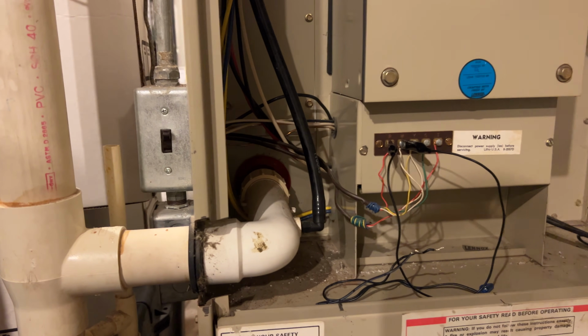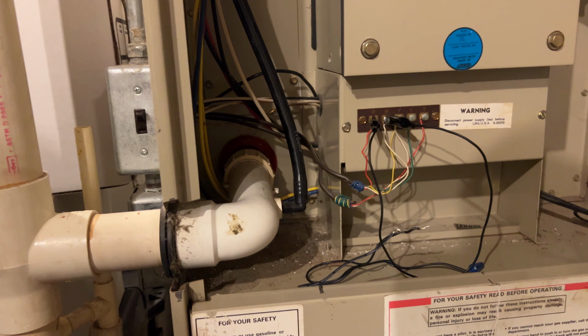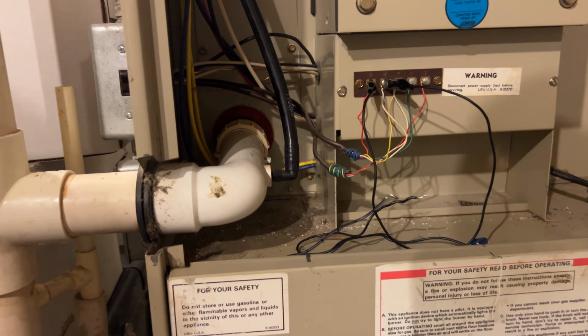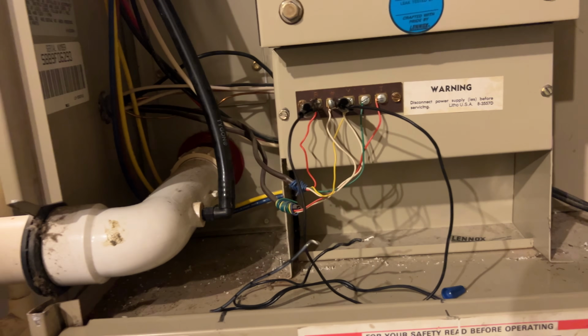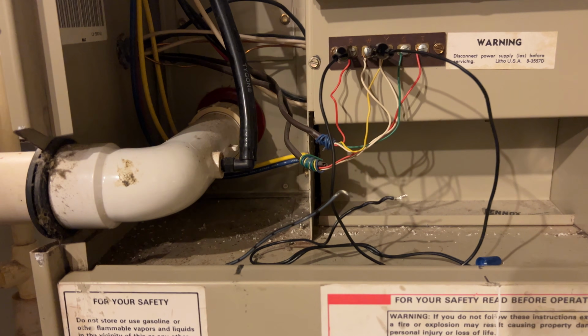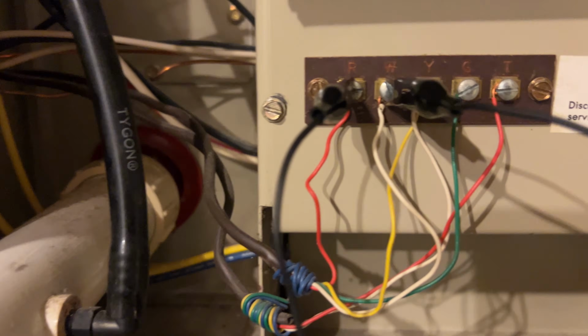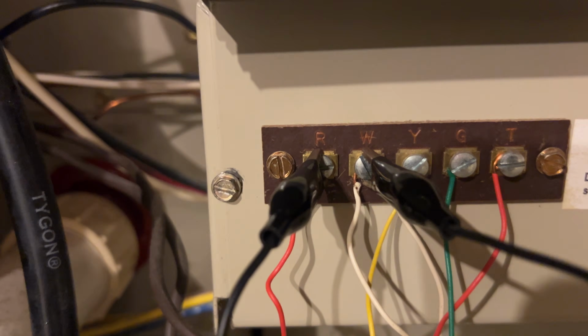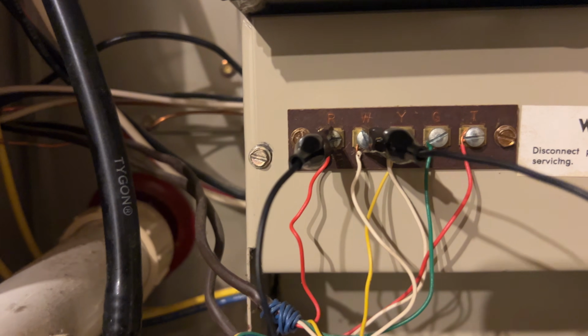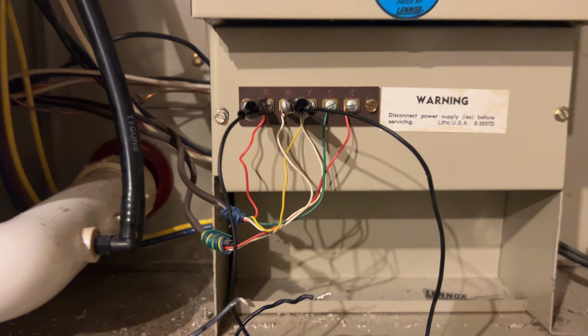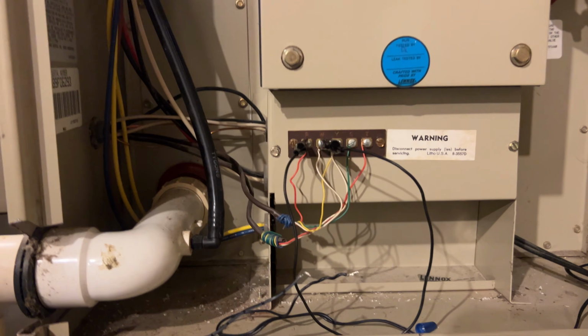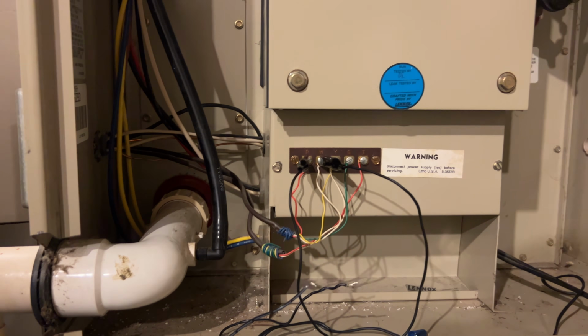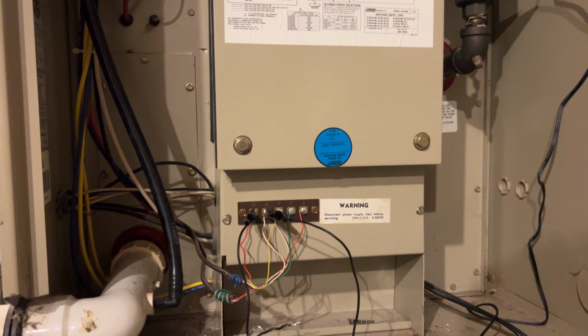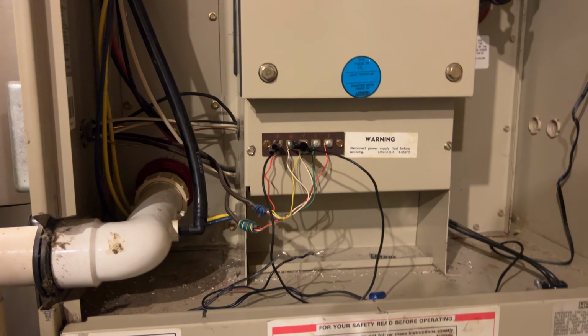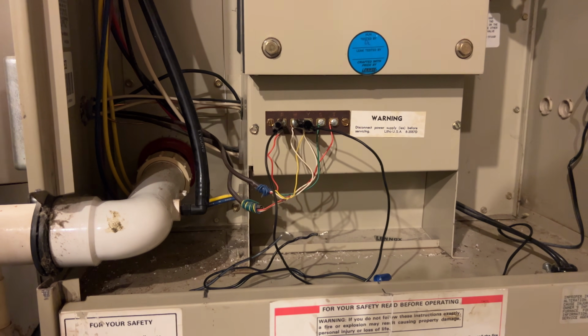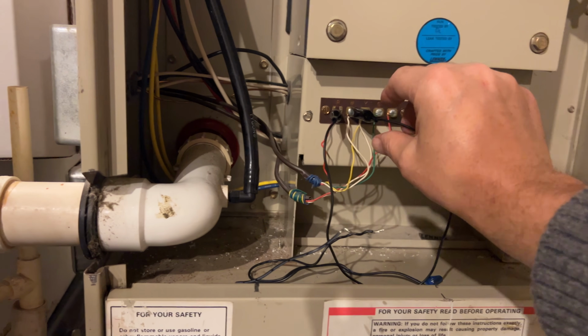I'm thinking now that possibly when I installed this new thermostat, maybe I mixed the wires up, or did something I shouldn't have. But you can see right here, red goes to white, and that's how we have it shorted. That's when it's calling for heat, those things have to be shorted. So let's go look at the thermostat and make sure we've got everything wired properly. But we're gonna kill this — I'm gonna simulate the thermostat turning off the heat call by just unplugging it.